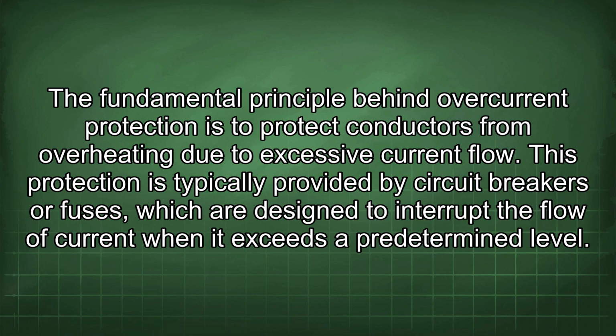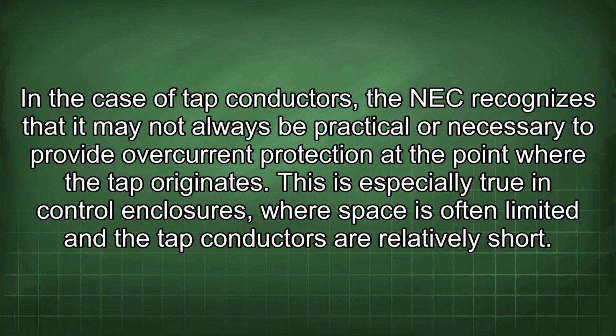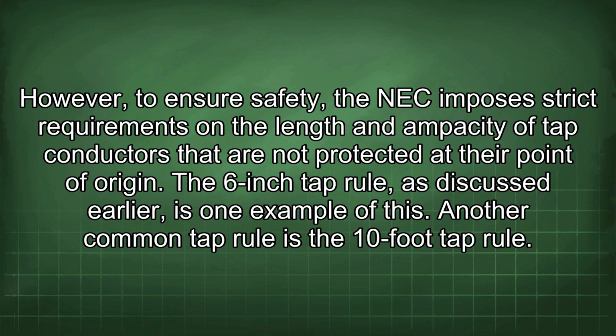This protection is typically provided by circuit breakers or fuses, which are designed to interrupt the flow of current when it exceeds a predetermined level. In the case of tap conductors, the NEC recognizes that it may not always be practical or necessary to provide overcurrent protection at the point where the tap originates. This is especially true in control enclosures, where space is often limited and the tap conductors are relatively short. However, to ensure safety, the NEC imposes strict requirements on the length and ampacity of tap conductors that are not protected at their point of origin.